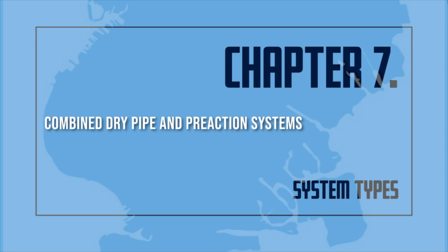Combined dry pipe and pre-action systems. These systems have the basic features of both types of systems. The piping system contains air under pressure. A heat detecting device opens the water control valve and a quick opening device. The system then fills with water and operates as a wet pipe system. If the heat detecting system fails, the system will operate as a standard dry pipe system.